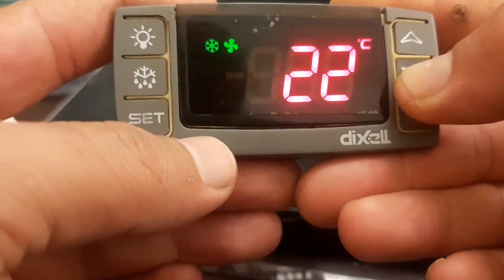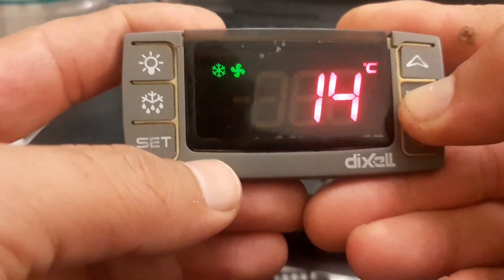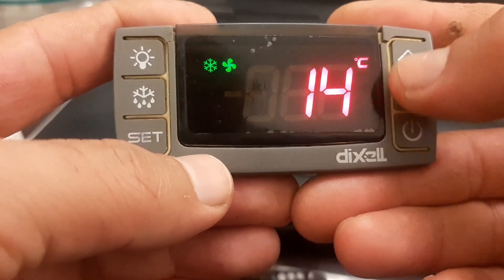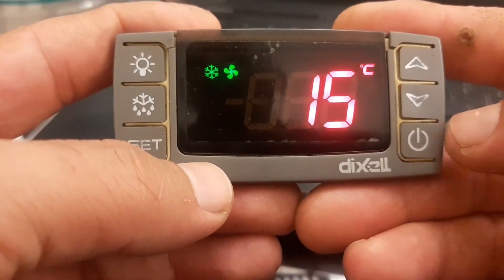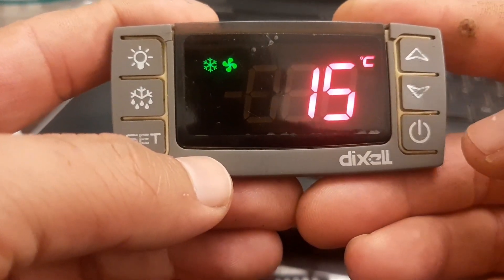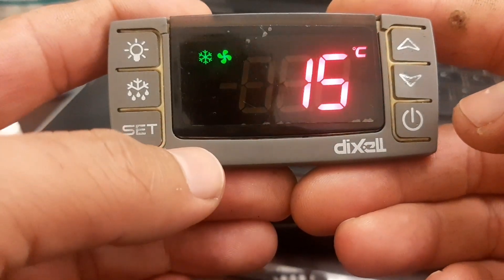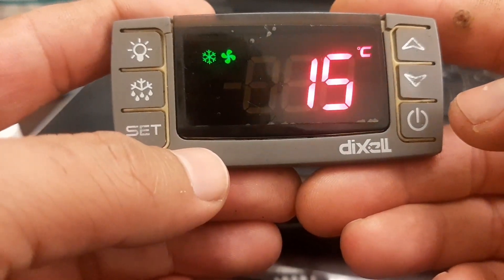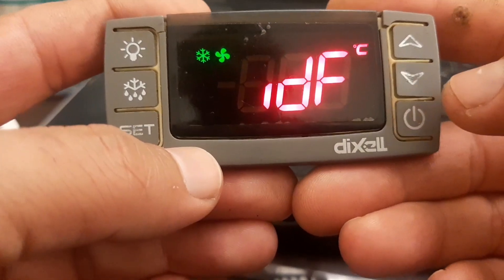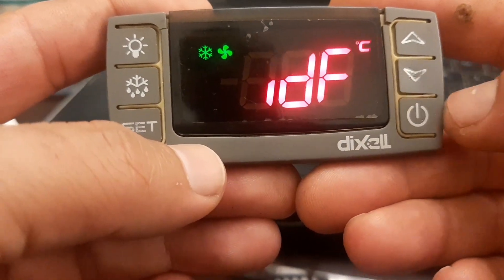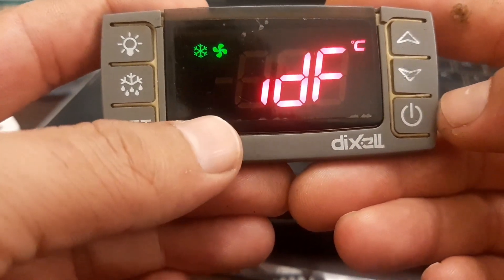The next setting is DTE - defrost termination temperature. Normally you can keep this at 10 to 15 degrees. For example, I set it to 15 degrees. When my evaporator temperature reaches 15 degrees, the defrost will terminate.